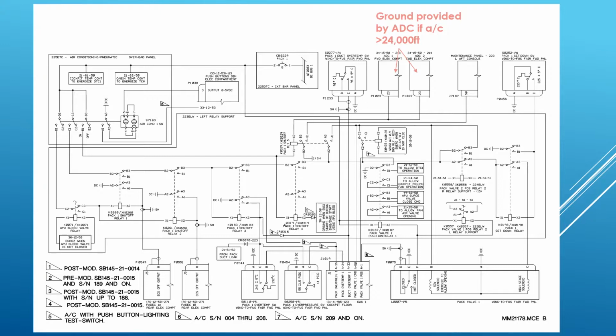The other first 2 are linked into the FADEC. So this is what causes the pack to shut down if we're in the takeoff 1 rating. The FADEC knows what rating we're in. The relays don't. So the FADEC is in charge of those 2 relays, and if we're in takeoff 1 and we advance the power levers, when we get to the takeoff position, the FADEC will provide a ground signal to these relays, and these relays will energize.